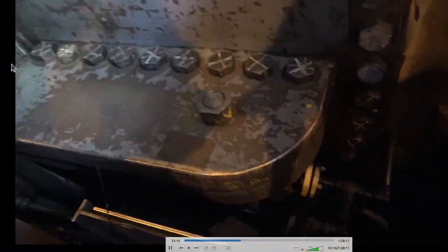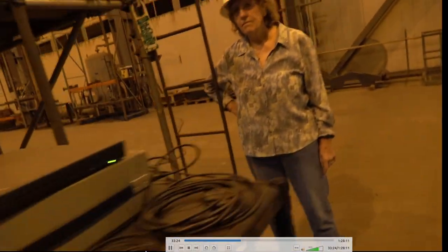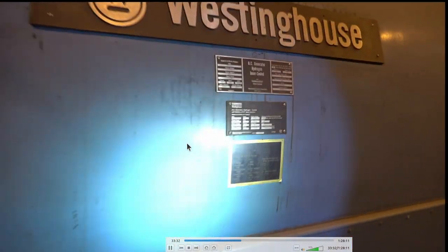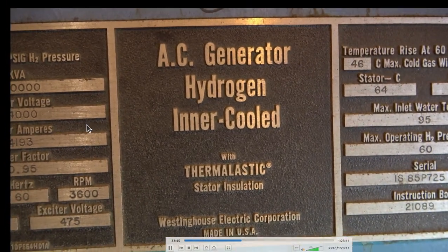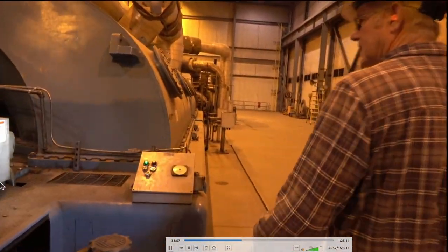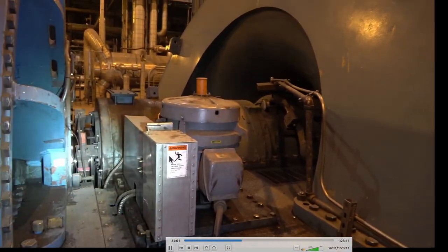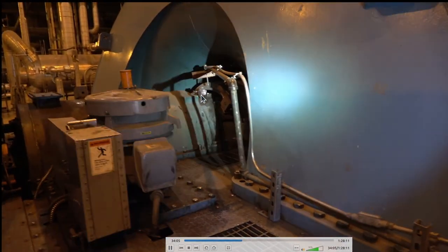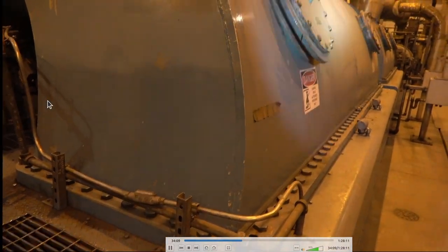Your seals sit back in here on the generator. Part of the seal oil is back underneath there, sealing the generator. Here's the nameplate on the generator — you can pull over 14,000 amps out at 24,000 volts — that's quite impressive. Turning gear sits back here. When the unit sets down, you have to keep it on turning gear so you don't bow your rotors — the bottom is cold and the top is hot, and you can do damage. So as soon as it slows down it goes on turning gear, and your lift pumps run to make sure the shaft isn't rubbing on the bearings.